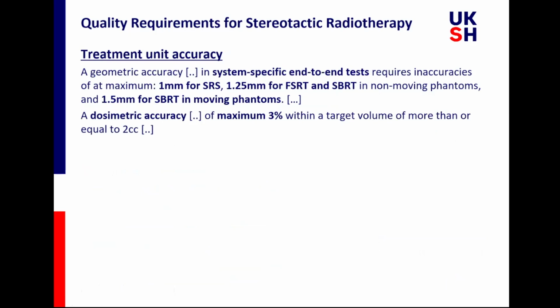The treatment unit itself, geometric accuracy of the system needs to be 1 millimeter for stereotactic radiosurgery and 1.5 millimeter for extracranial SBRT. And this needs to be verified by system-specific end-to-end tests. That's what we do, of course, during commissioning of our systems, and routinely every month or even every day that we check these accuracies. And the dose accuracy needs to be within 3% in the target itself, measured with dosimetry systems that are useful for small field dosimetry.